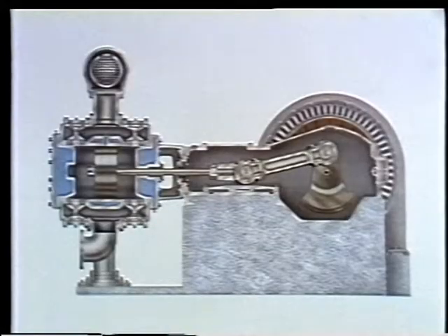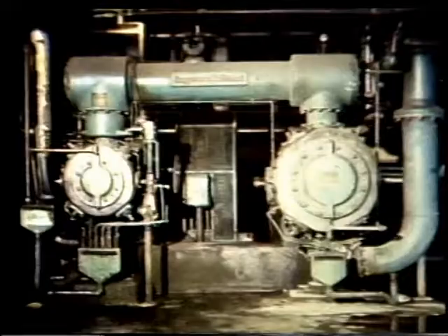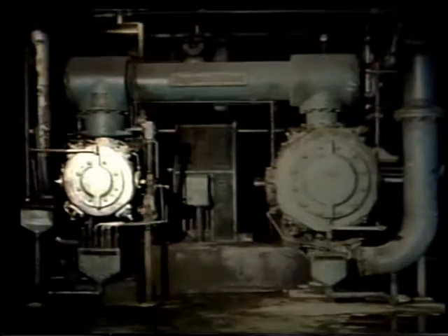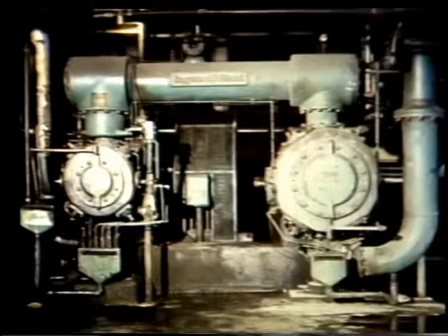This cutaway side view enables us to see the internal parts of the first stage. As we said, the second stage is constructed identically, except that the cylinder and the valves are smaller. The second stage cylinder can be smaller than the first because the air from the first stage has already been compressed into a smaller space.